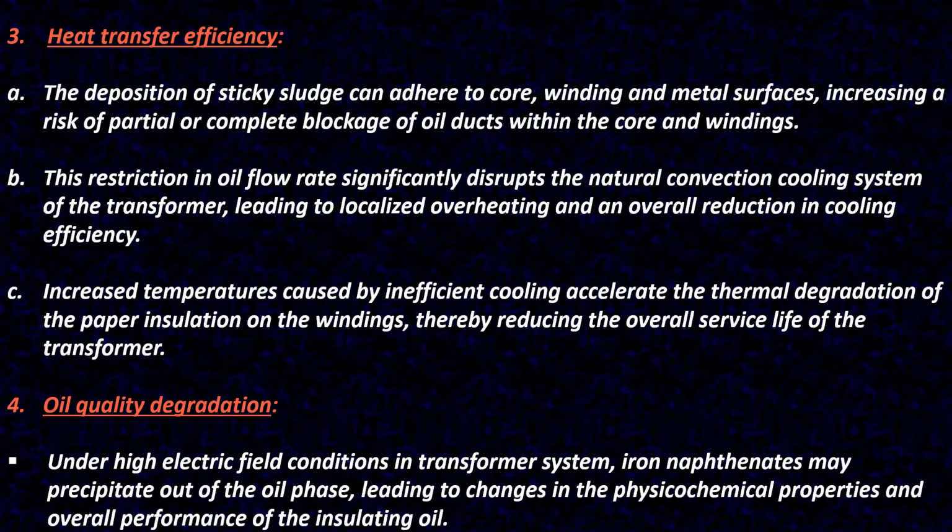Heat transfer efficiency. The deposition of sticky sludge can adhere to core, winding, and metal surfaces, increasing the risk of partial or complete blockage of oil ducts within the core and windings.